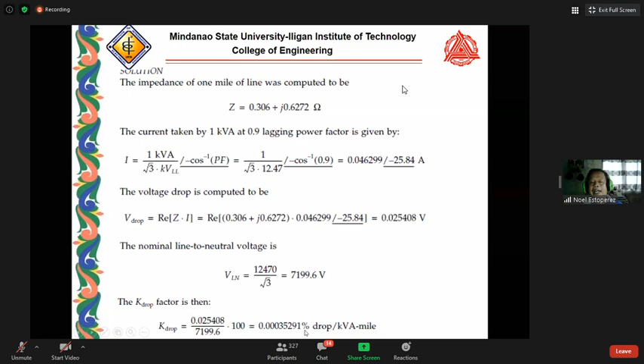So the application of the K drop factor is not limited to computing the percent voltage drop down one line segment. When line segments are in cascade, the total percent voltage drop from the source to the end of the last line segment will be the sum of the percent drop in each line segment. Okay, so this is the problem.